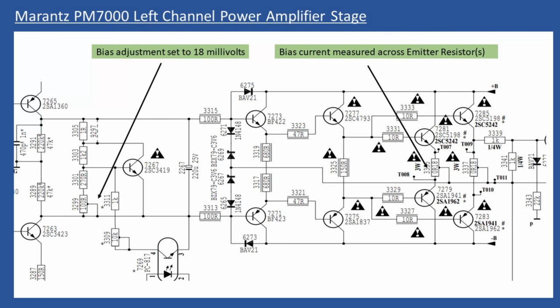Then put it back to roughly the position that it was previously, power up the amplifier, and then of course you can make your adjustment. And what you'll find is that the adjustment that you make here, because these preset potentiometers are not multi-turn like 10-turn, they're single track, it's just going to take you a little bit of time. Just make a small adjustment, then wait, and what you'll find is the millivoltage will increase or decrease depending on direction, and then it will start to stabilize, and then you can repeat the adjustment until it's approximately 18 millivolts.